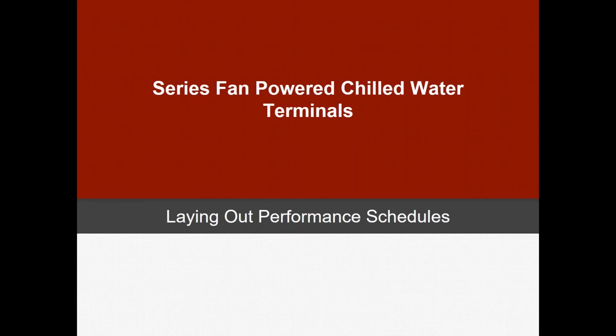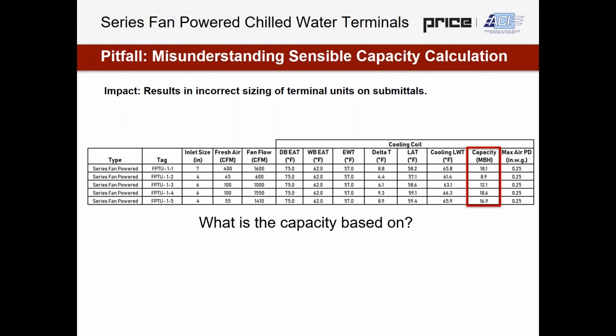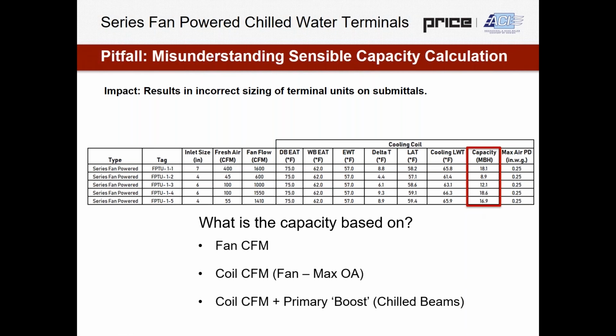So the last thing I want to show before we have a question period would be specifically looking at laying out some performance schedules, which is something that ACI and Price are happy to help with in the design stage of this kind of equipment. So it's a major pitfall with this equipment, kind of the misunderstanding of sensible capacity calculations. If we see below, we have this table here. This is often the kind of table that I'd be seeing with this kind of equipment provided. So the typical kind of performance and equipment schedule. And it would have a cooling coil section with a capacity called out. Now, it's not always communicated what this capacity is actually based on.